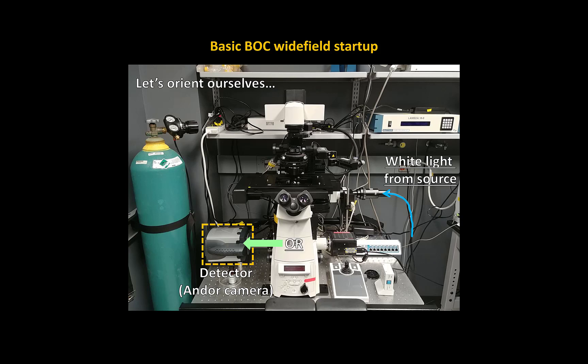Alternatively, you can send that light to the right side here and to our Hamamatsu camera. This detector is really good for fast imaging experiments — so if you're doing calcium dynamics, for example. It doesn't have quite the sensitivity or ability to detect light as our Andor camera does, but if your sample is bright and you want to get really fast information, the Hamamatsu camera can provide that better than the Andor camera can.